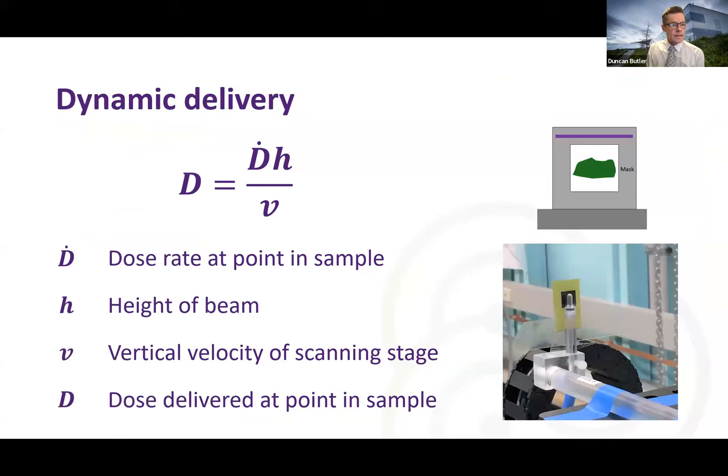So dynamic delivery. The dose everywhere in the field is given by the dose rate times the height of the beam, the static beam, divided by the velocity. It's pretty easy to work out this formula. It does make it a bit confusing when you're in there. The faster you scan, the lower the dose. It's a little bit of an inverse calculation. But this is the formula we use for doing dosimetry, relating the dose rate to the dose in the sample.